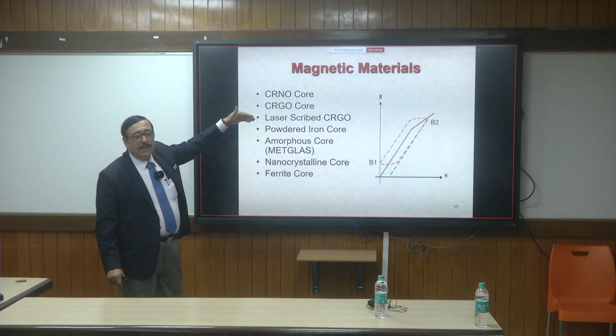So what happens is, if you use a CRGO type of core at higher frequency, the losses in that core, both eddy current and the hysteresis losses, become so large that you cannot handle the loss. So the only alternative is this: loss is dependent upon frequency and the flux density. Frequency is something which you can't change because that's the application. So you try to reduce the flux density. So as you reduce the flux density, the size increases for the same transformer.